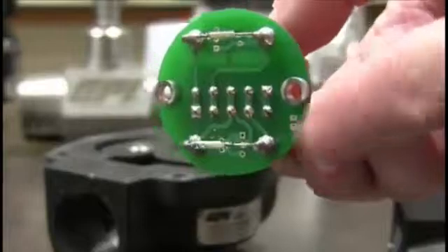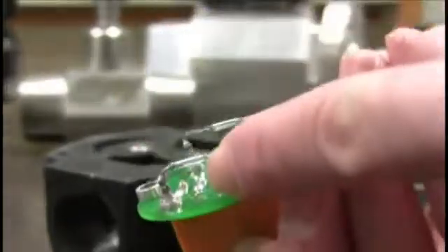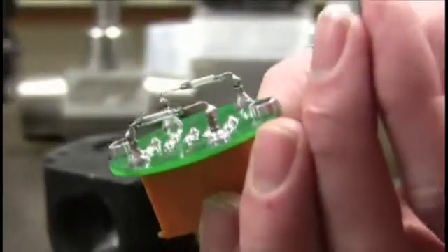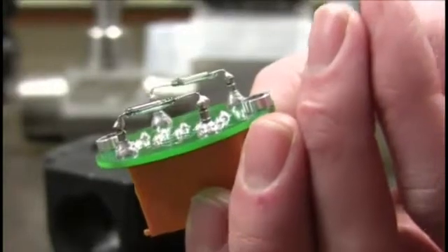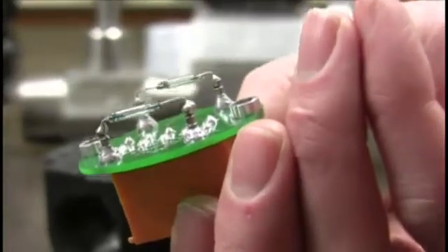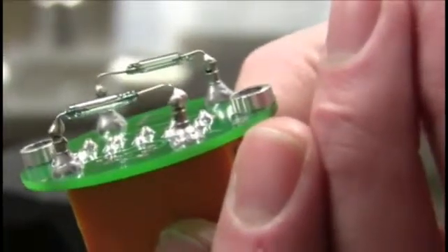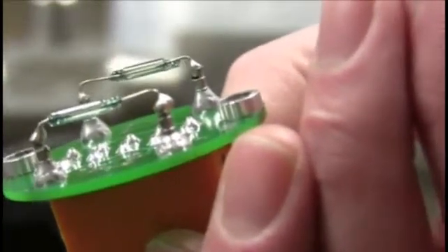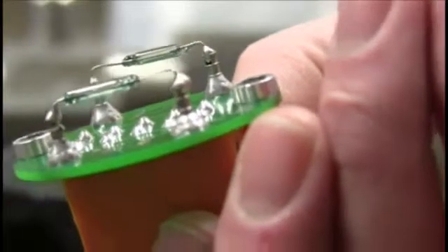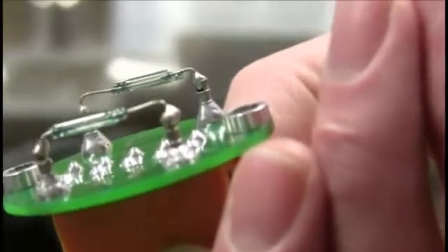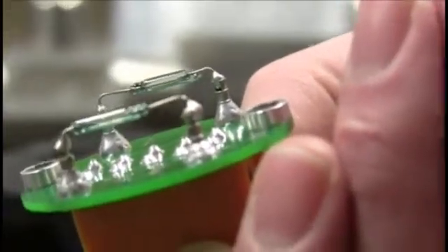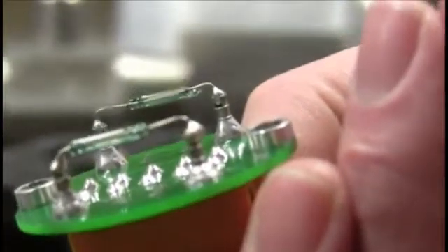As you can see underneath, you've actually got two reeds. One here is like a little glass tube, and inside that glass tube is a real thin wire, and that thin wire will bend down every time the rotor goes underneath it, and the magnet draws it down, and it'll touch a stiff hard wire, and that gives it continuity. And then once the magnet's gone, the reed or the thin wire straightens back out.